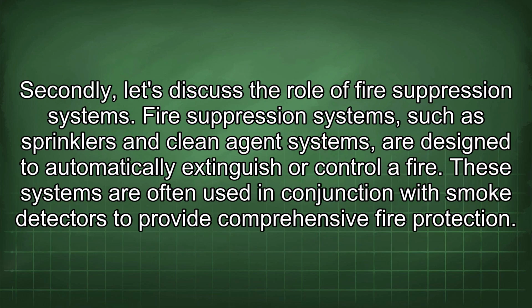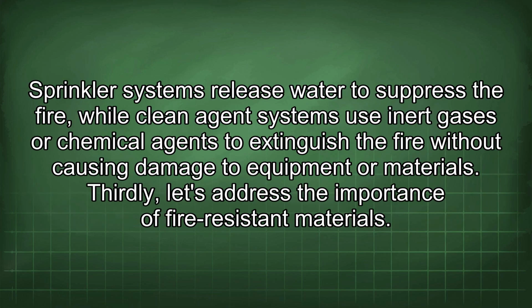Secondly, let's discuss the role of fire suppression systems. Fire suppression systems, such as sprinklers and clean agent systems, are designed to automatically extinguish or control a fire. These systems are often used in conjunction with smoke detectors to provide comprehensive fire protection. Sprinkler systems release water to suppress the fire, while clean agent systems use inert gases or chemical agents to extinguish the fire without causing damage to equipment or materials.